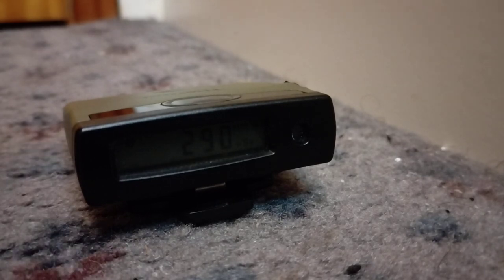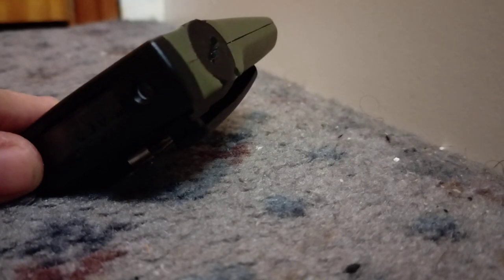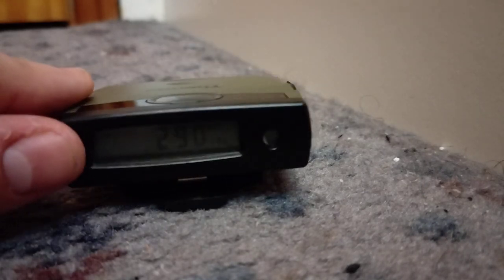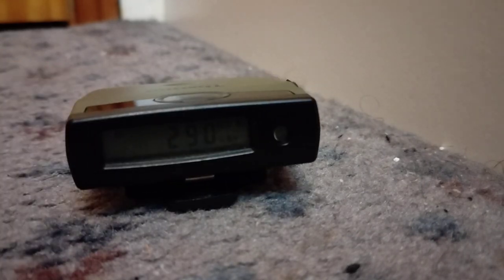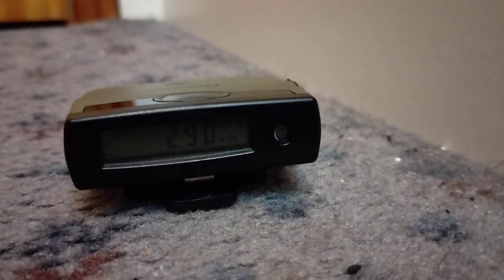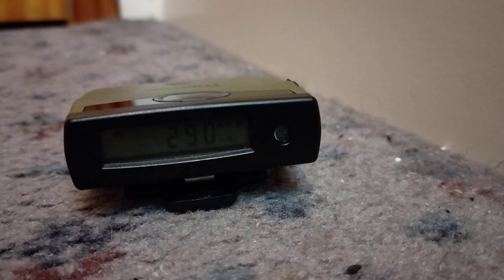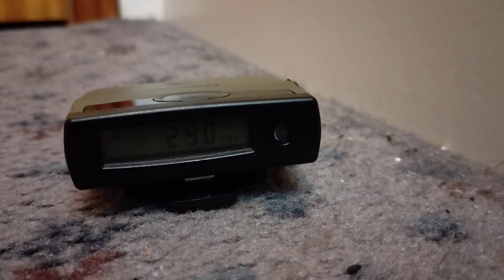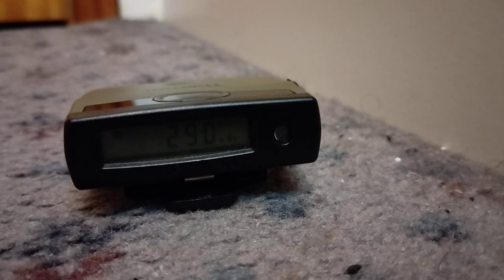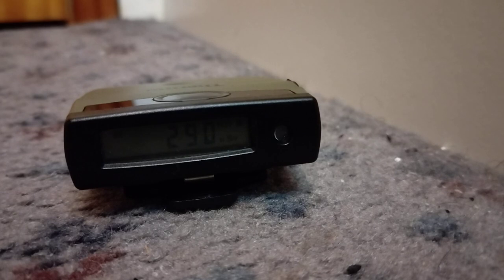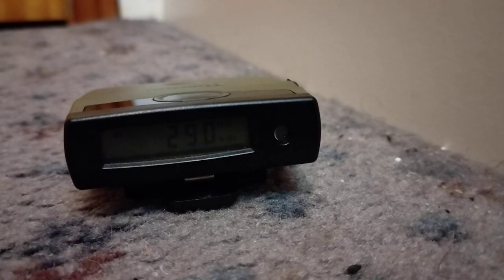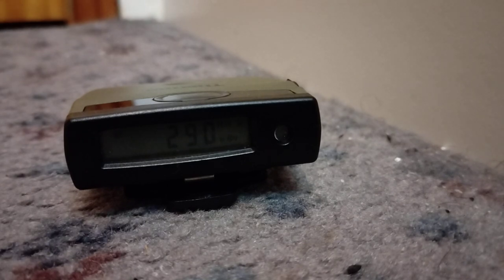So these are good devices, don't get me wrong. Runs on a single AA battery. I found both rechargeables and alkalines work fine in there, so 1.2 to 1.5 volts. But as I said, the only problem with this is that without proprietary software, you can't reset it, it seems, because it was designed so workers couldn't reset their total dose. The idea is that only an admin type person can reset them, not the actual individual workers.